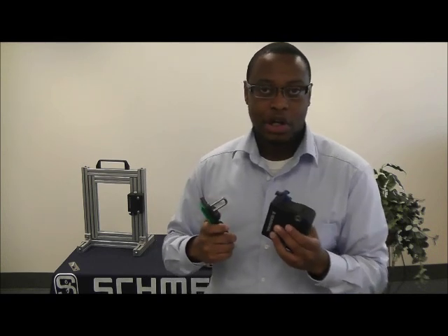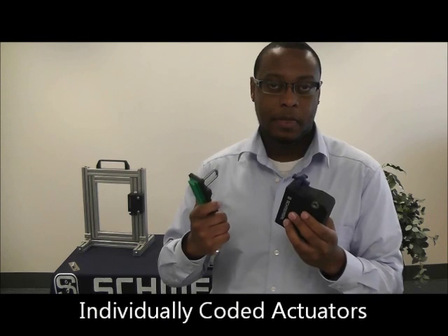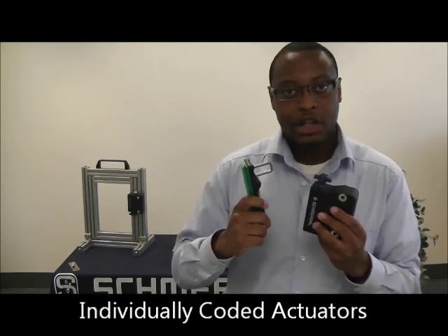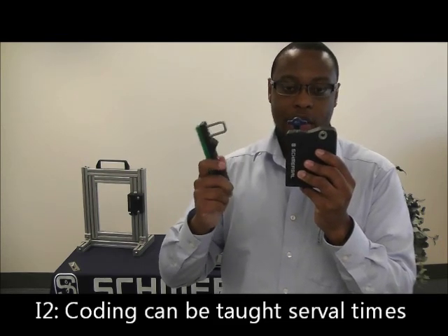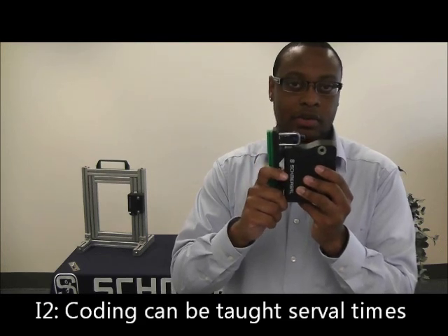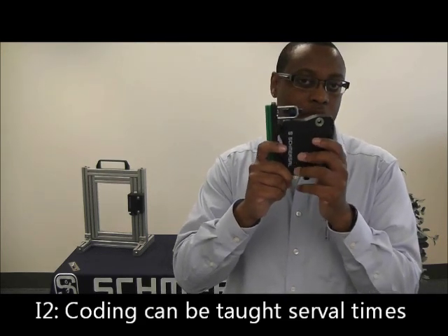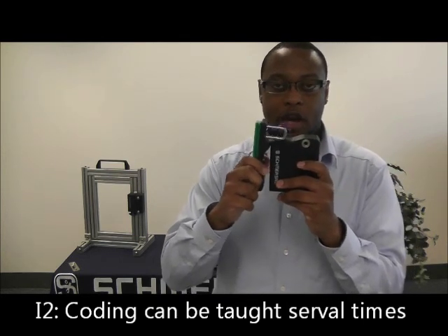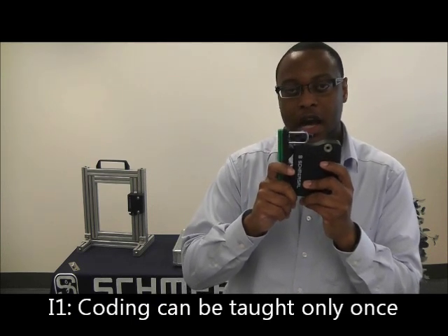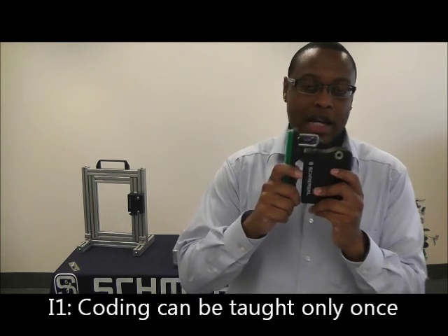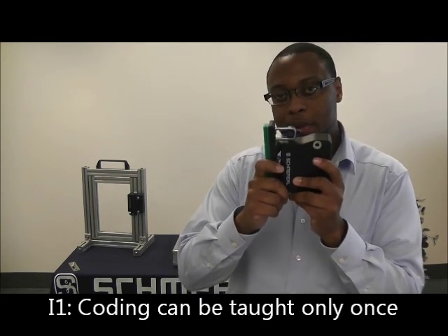Another option for the AZM300 will be for an increased tamper-proof environment, so if you have the need where you have to have an individually-coded key, we offer that with the i2 version. Now with that, you take the AZM300 and an individually-coded actuator and teach it in to the AZM300, and only that actuator would be able to deliver the 24 volts for your safety outputs. And if you happen to damage or lose that actuator, you can order another individually-coded actuator and teach that in with the AZM300. There's also another option for an even more increased tamper-proof environment where you can only teach in one actuator to the AZM300, and that's with the i1 option. And if for some reason the actuator is damaged or gets lost, you have to replace both the AZM300 and the actuator.